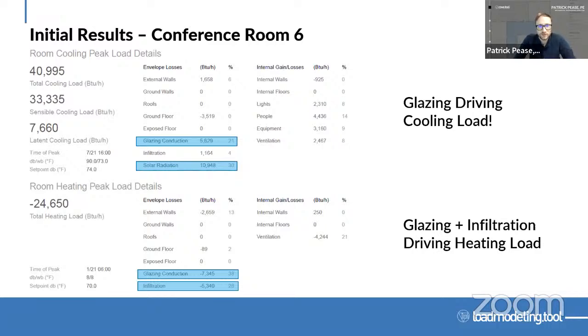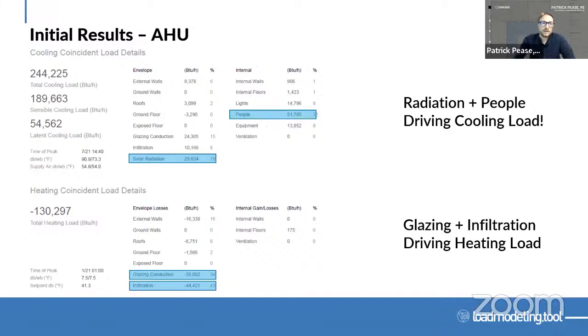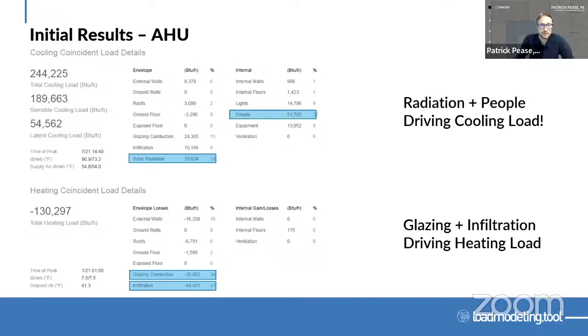Looking at the conference room first, I can see right off the bat the things driving my load are the glazing and the solar radiation. That's actually very similar on the heating side — glazing conduction and infiltration are driving the heating load. Looking at the whole building at the AHU level to see what's driving the whole building load: I can see radiation is one thing, and people is the other aspect driving the load. For heating, glazing conduction and infiltration match between that one room and the whole building.